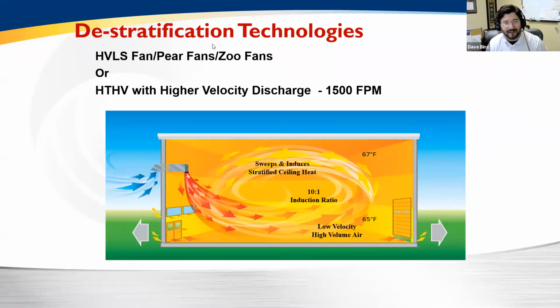But with our HTHV technology we use high velocity, and we actually induce a large air turnover or air mixture of that warm, stagnant air at the ceiling and help mix and push that down to the floor. So with a very small CFM, I can get large air movement and good air mixing. If I mix 10 parts room air with 1 part 160 high velocity air, by the time it hits the floor it's a much more average temperature of maybe 75, 85 degrees, and I get good air mix and destratification without needing to add a lot of other ductwork or recirculation fans, all inside that same device.